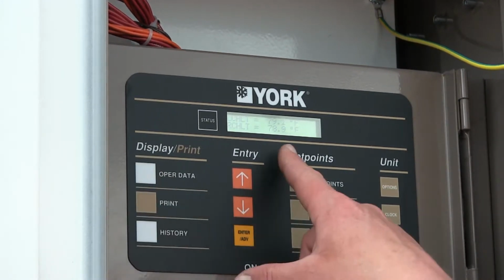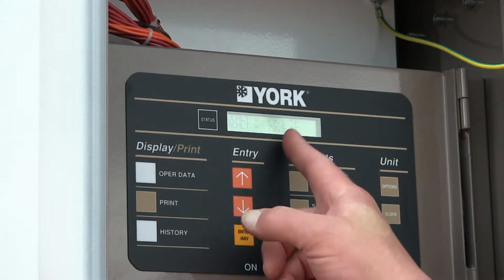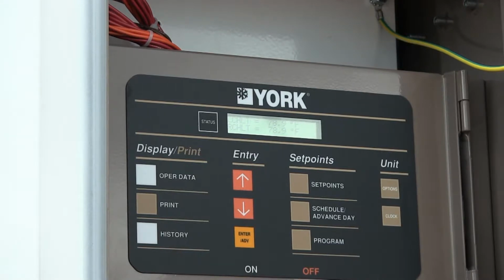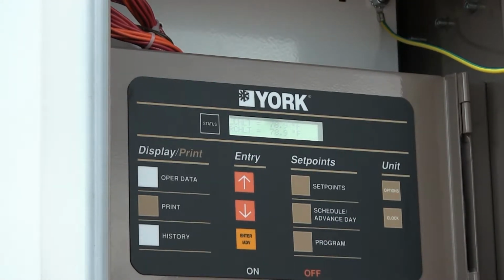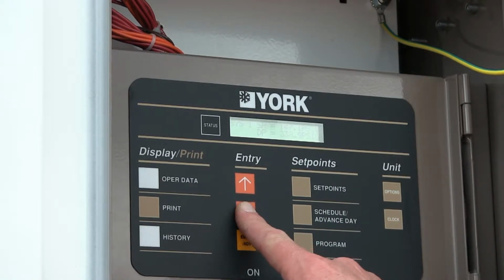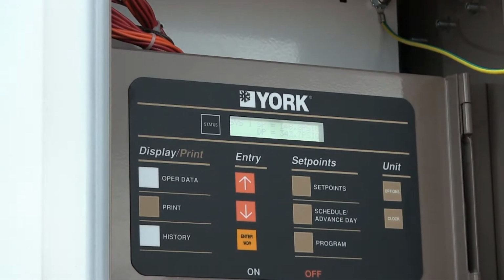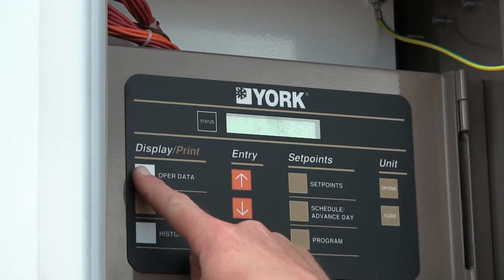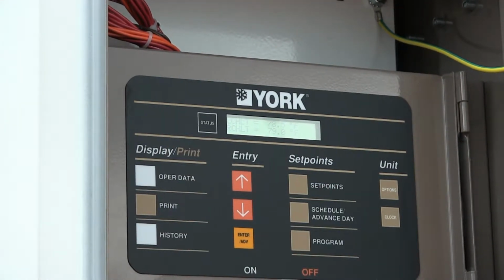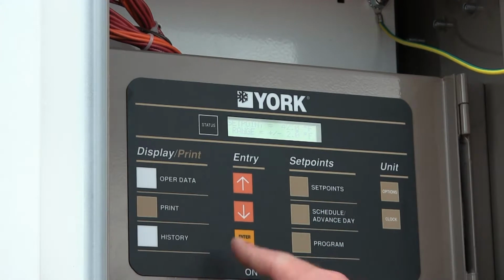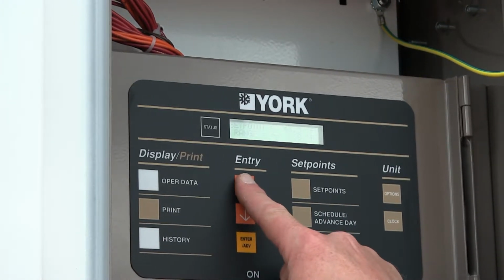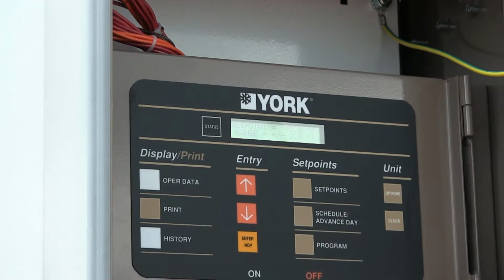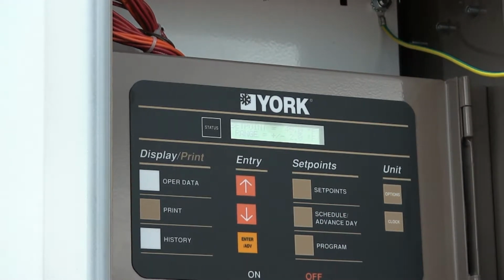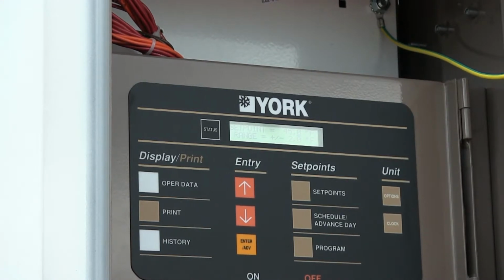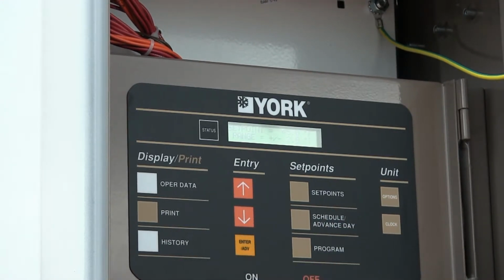Let's walk over here to operator data and we'll start watching our water temperature. Currently the return is at 79 degrees and now you see the leaving water temperature starting to drop. And you can certainly go down and look at your refrigerant pressures. Everything you need to work on the machine is contained within the main display. But we can go back to the operator data and you'll see that we're starting to drop the temperature on the leaving liquid side. And if I want to change my set point anytime, I just simply punch the set point button. I raise that up to 44. 45 degrees is our standard design that we use for our air handlers and most of our comfort cooling operations. Unless it's in a low temperature situation, you're going to typically default to 45 and you push enter.